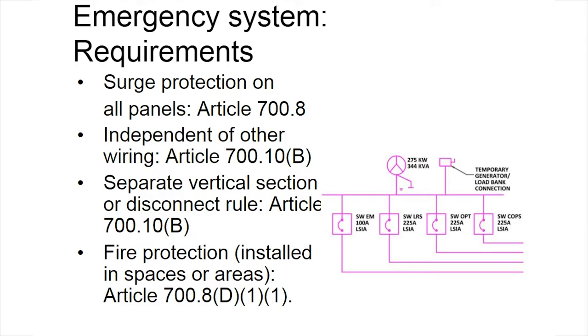Now, the diagram at the right shows the generator feed for the hypothetical one line with a single conductor from the generator to a standby system wireway and separate disconnects serving the emergency system and the rest of the systems. This requirement appeared first in the 2008 edition. It's usually not enforced retroactively, but it will apply to additions to existing systems. It can make it impossible to add, say, an optional load to an existing switchboard that may not have space except on a section that serves emergency loads.